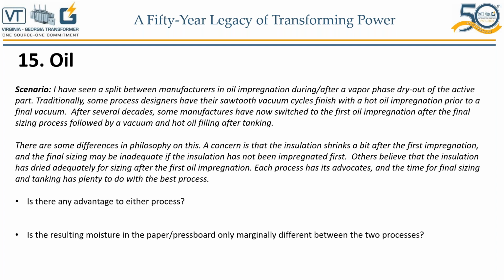And then you take that active part, go in the tank, or if it's a bell tank, put it at the base and then put the tank around it. Nonetheless, all this takes time, especially if it's a large LTC, load tap changing, transformer. Imagine a 200 MVA LTC transformer. All that process takes time, so we will have surface moisture. It may take 10 hours, 12, 18, 24. I don't know, it depends on the plant.